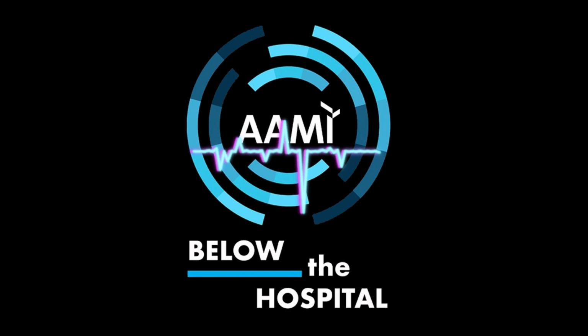For a lot of people, they don't think there is an ethylene oxide option for hospitals right now, and that's simply not true. There's some new systems on the market that are highly gas efficient. They use 90% less gas than anything that has come before them. And the latest of these systems were cleared by FDA in 2020. So you could say in a lot of ways, these are the newest sterilizers on the market.